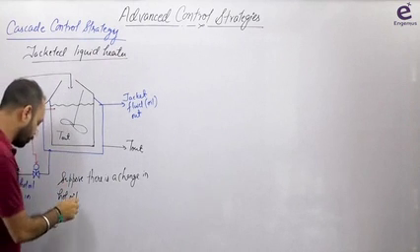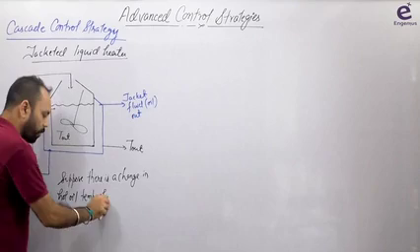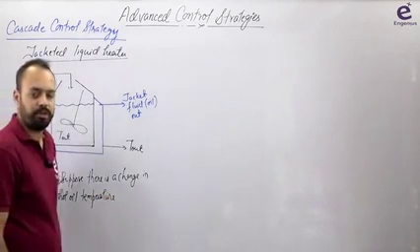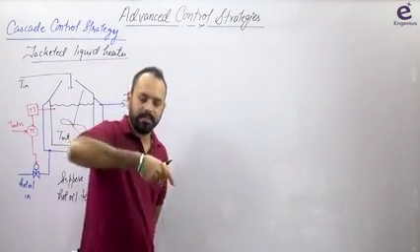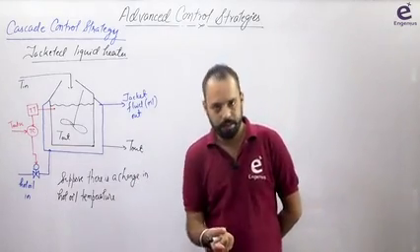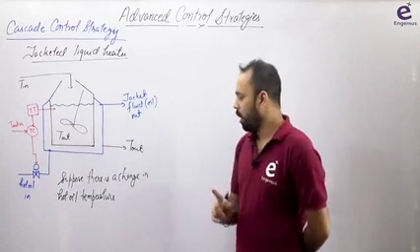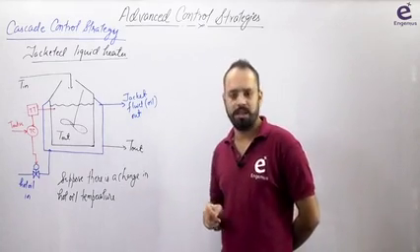If there is some disturbance there, hot oil temperature, आप बोलोगे सर वॉल्व है ना कंट्रोल करने के लिए, बट वॉल्व इज नॉट कंट्रोलिंग द टेम्परेचर ऑफ द हॉट ऑयल. भाई वॉल्व को बंद करने से क्या टेम्परेचर कम हो जाएगा? नो, वॉल्व कैन ओनली कंट्रोल द फ्लो रेट. वॉल्व इज कंट्रोलिंग द फ्लो रेट, बट सपोज if the hot oil temperature is changing, then what is going to happen?